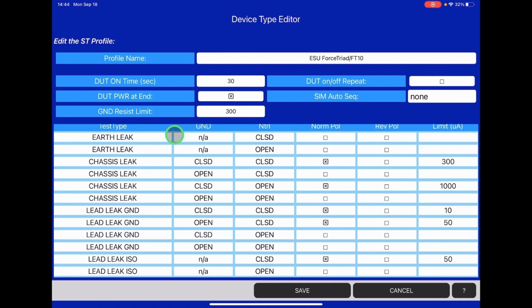And below that are the electrical safety test sequences we can perform. You have a choice of running a variety of earth leakage tests, chassis or enclosure leakage test, a lead leakage to grounds test, or a lead leakage source test, as may be referred to, or a lead leakage sink test, which is also commonly known as a lead leakage ISO or a lead leakage main and applied parts test.